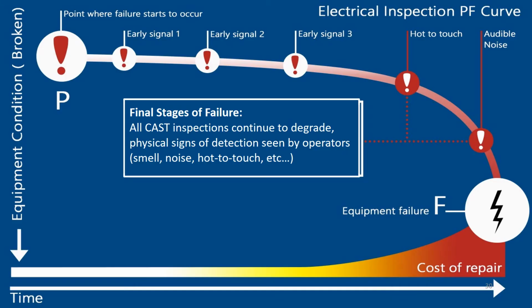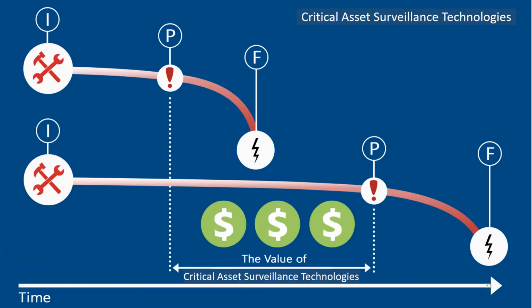So if you enable it to just go on in the PF curve, now you're going to start to come into the other issues. If things get hot to touch, the audible noise, so mechanical and audible failure are going to be very evident. And again, if you look at it, the cost of repair. The longer you leave it, the worse it gets, the more expensive it gets to repair, to such an extent where it just isn't feasible to carry out the repair, and you're doing a complete asset swap.